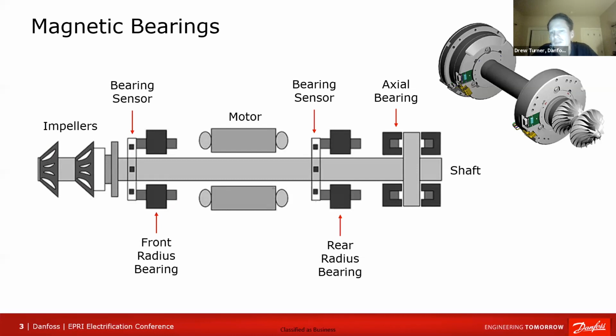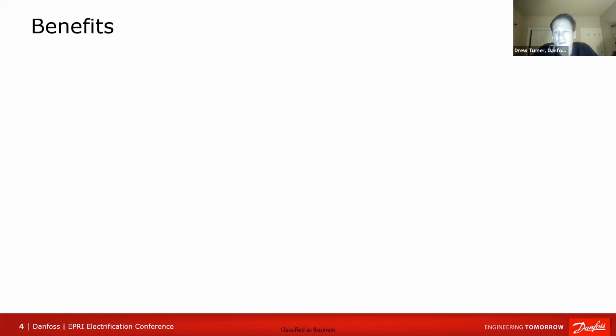So it's a very different technology, but that was utilized to drive it to be an oil-free compressor. That was the number one issue that he saw that he was trying to solve with the new compression technology, is eliminating the oil in the system. And that's on the front end of the compressor, the compression process itself. You also have to solve that same issue on the back end of the compressor. And Vladyslav is going to be talking about this later as well. But how you do that is with different technologies. And Thomas touched on this ahead of the presentation, but there's other technologies that you can utilize for it. But the one that he started with was magnetic bearings, which was being experimented with in the oil and gas industry at the time, 25 years ago when this was invented. But the combination of centrifugal or dynamic compression, along with the magnetic bearings, enabled going oil-free, which was the number one issue that he was trying to solve at that time.